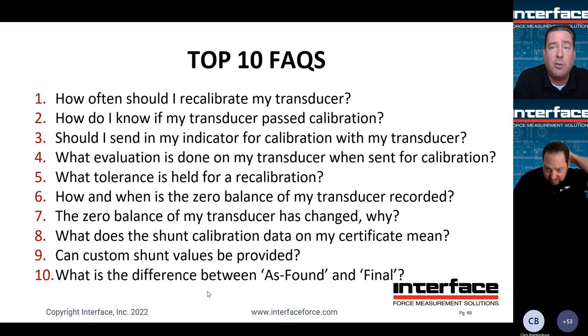What evaluation is done on my transducer when sent for calibration? So we perform a couple checks. Number one, it's a bench evaluation. We perform a physical inspection of the load cell, look for damage, step number one, and then document the as received condition. We then perform a series of bridge evaluations using both an indicator and then taking resistance measurements off the bridge. What we're looking for there is any potential electrical symptoms of mechanical overload or damage.